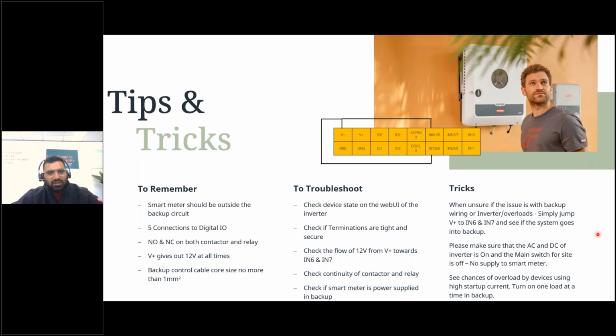So one of the things you can check is the device state. On the web UI of the inverter, you have overview, which shows real-time what is happening at the inverter. Next to it, you have device state, which tells you whether the inverter is running, starting, or not running. Normally, when the backup's not working, the inverter will try to tell you why it hasn't gone into backup. An example would be the message, no feedback from relay or no feedback from contactor. And a lot of times we find that it is just a poor termination, so maybe a loose connection.